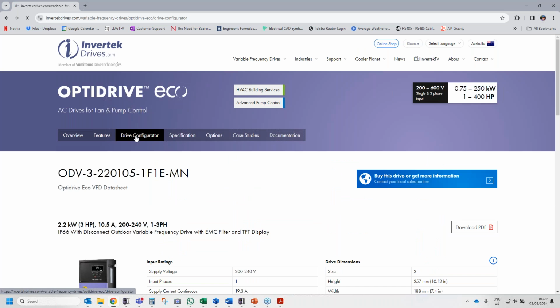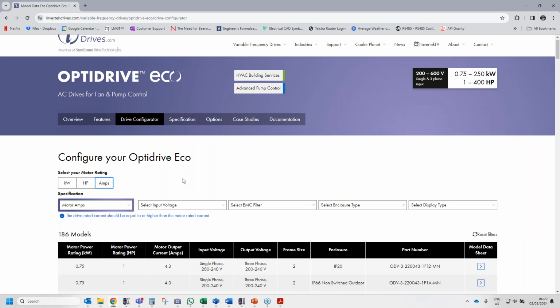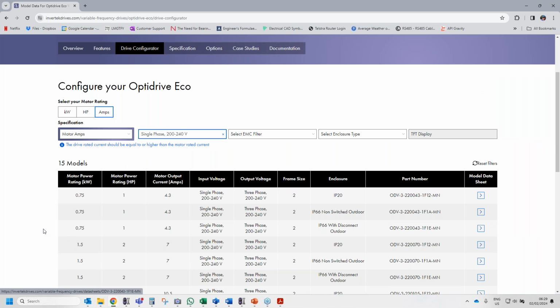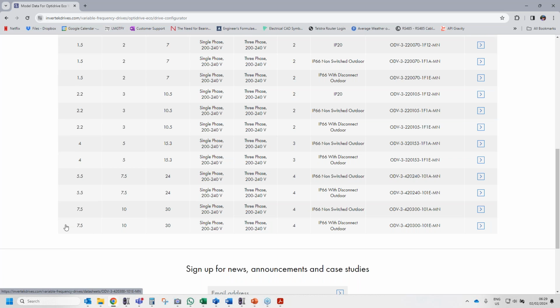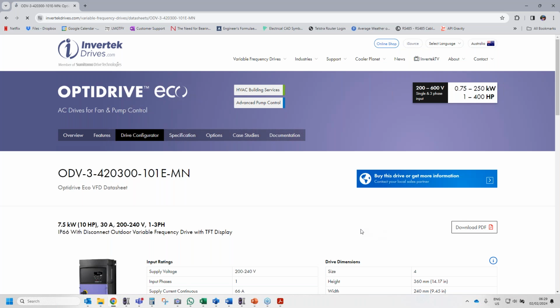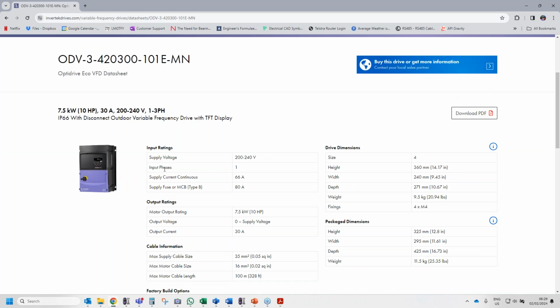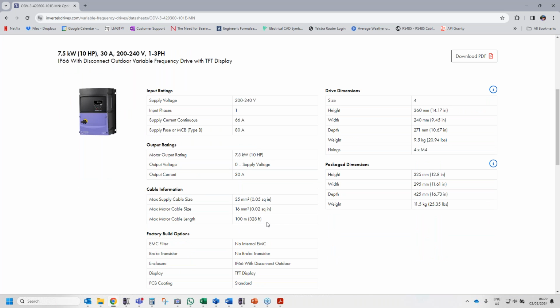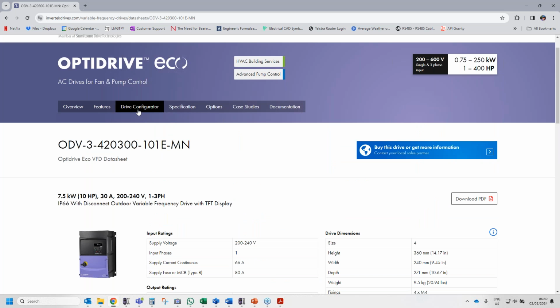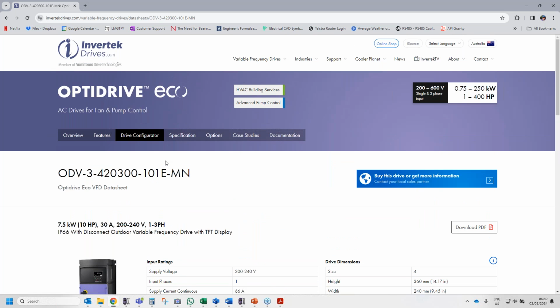So if we go back, we'll start another one. If we select the input voltage, single phase to 3-phase, then you can see we go up to 10 horsepower, 7.5 kilowatt. So there's your supply voltage, there's your input phases, there's your output ratings. 7.5 kilowatt, 10 horsepower, output voltage 0 to supply, and that's a 3-phase output. We can do the same thing with the others as well. We've got the configurator in the P2, the E3, and the Eco.